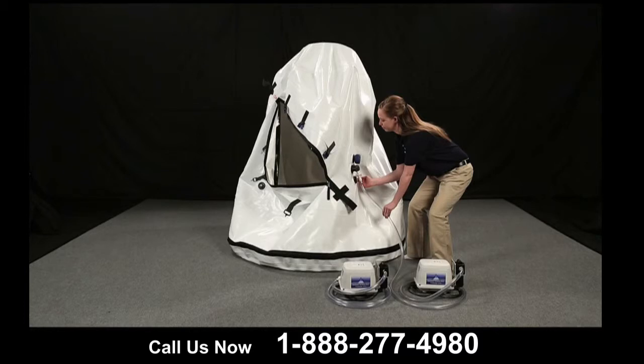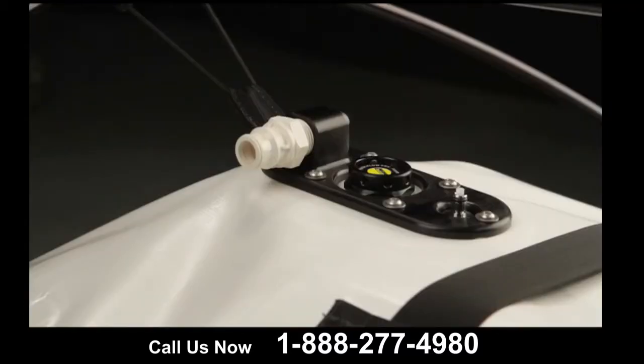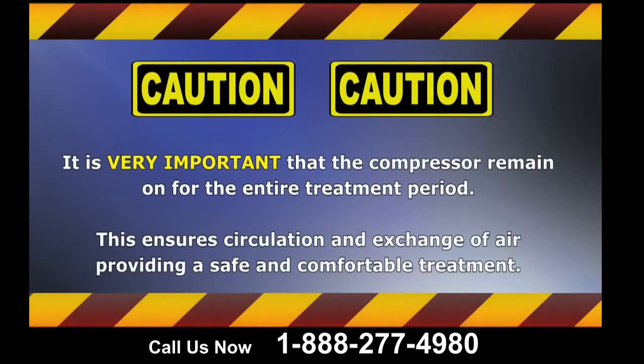Next, this is a fill valve where the compressor hose will be connected. This connection is called Quick Disconnect. The hose simply snaps into its fitting on the chamber. Please note, it is very important that the compressor remain on for the entire treatment period. This ensures circulation and exchange of air, providing a safe and comfortable treatment.